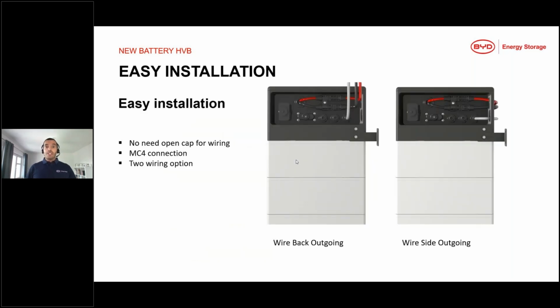The installation also is a lot easier than before. So the BCU, the head unit, is able to allow the installer to do external cabling without opening any panels, without trying to put some cables through some throughputs. Instead, every cable connection, it doesn't matter if it's DC or internet or grounding or the communication connection with the inverter, all of those connectors are standard connectors. So for DC, BYD is using MC4, and for communication, BYD is using RJ45. And with that, it's possible to have very easy installation of the cabling just within a few minutes.